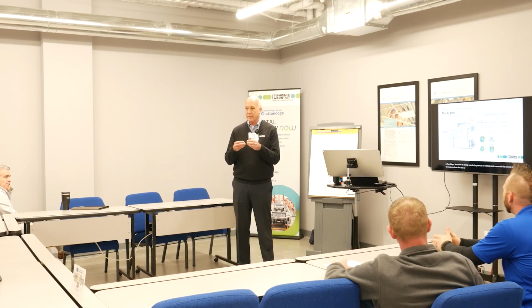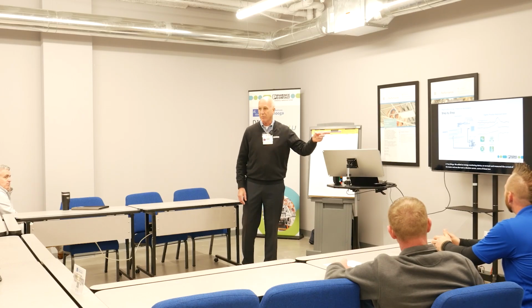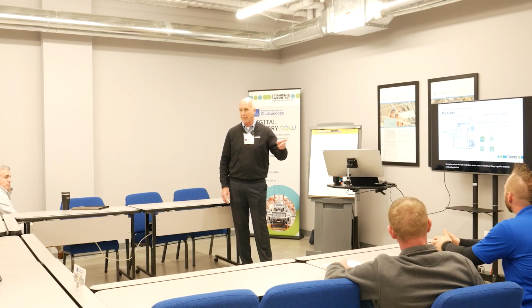Summing those two things together produced this plot on the right-hand side, which I call a signature. Each machine, as it operates and the press cycles, the current goes up and down but usually runs within norms. As bearings begin to wear or windings start to fail, you'll see changes to either the current or the vibration.